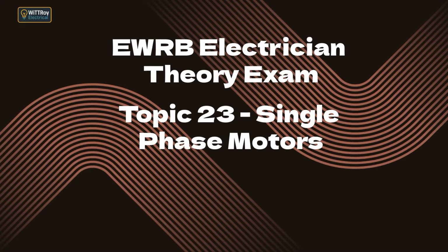Topic 23.3. Additional single-phase motors. A. Explain the operation and construction of the following types of single-phase motors. Now we look at 3 additional common single-phase motor types. Universal motor construction: wound stator and rotor, brushes and commutator, can run on AC or DC. Operation: because the stator and rotor currents reverse together, the motor still produces torque on AC.